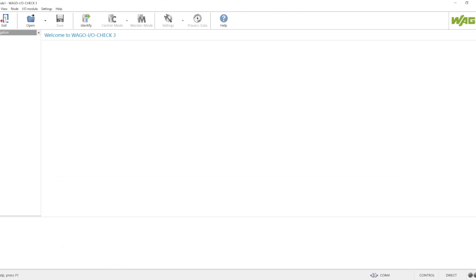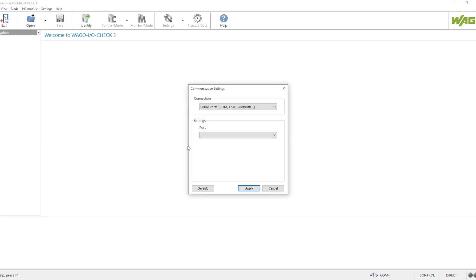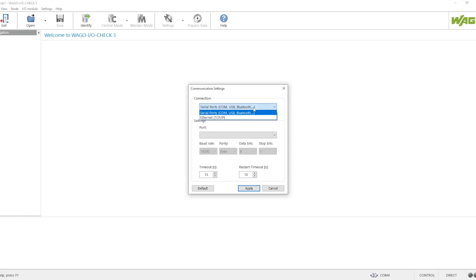We have a software called WAGO IO Check using which we can configure those IOs and also configure the controller. To connect using the software we have two options: one is serial using a serial port, and one is Ethernet TCP/IP. Using TCP/IP protocol you can directly connect by providing the correct IP. Using the serial port we need a special cable which comes from WAGO — USB to serial or serial to serial cables.